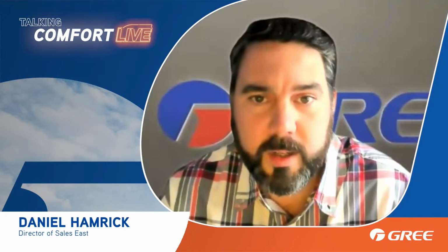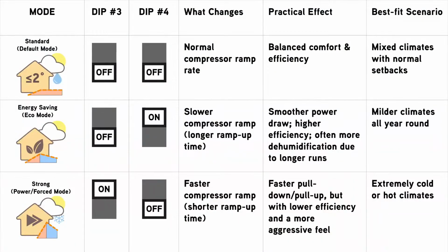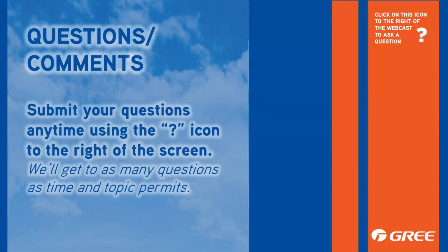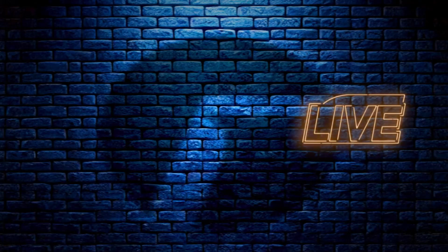I just want to clarify before we wrap up and move on. None of these dip switches are going to fix any ductwork issues or airflow problems. Or sizing issues, yeah, that's right. Which I believe is a little bit of a red flag that we use in tech support, right? If somebody says, "Hey, how do I set up strong mode?" it's like, okay, let's start asking more questions. Let's talk about why you want to set up strong mode. Let's go from there.